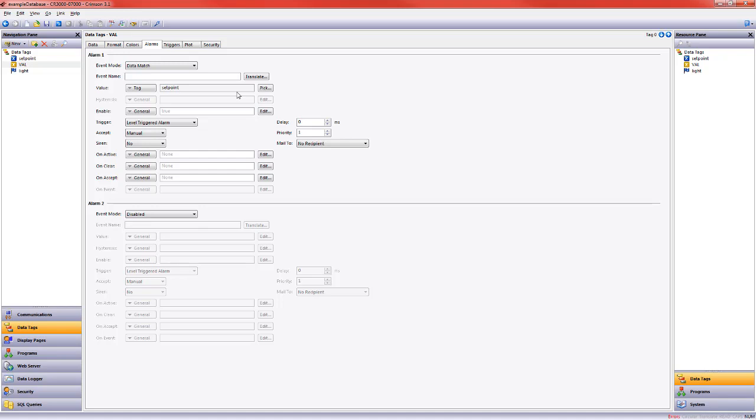Zero is going to be our comparison point until we use data entry to change that value. The next thing we want to do is give some diagnostic information to our operator in the form of the event name. The event name is what will appear in the alarm primitive we just created, as well as the text that would appear if you were going to send an email when there's an alarm event. So I am going to say value equals setpoint. This may include a diagnostic code of some kind that refers to something in a manual. The other thing I want to draw your attention to is this accept.